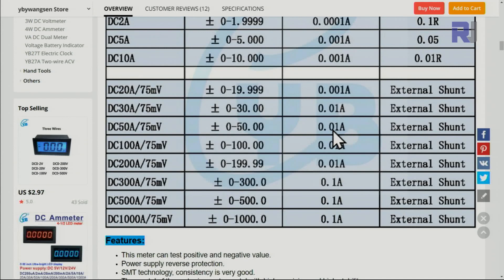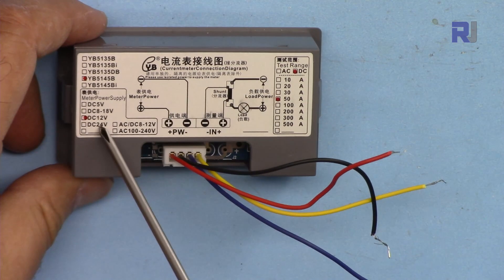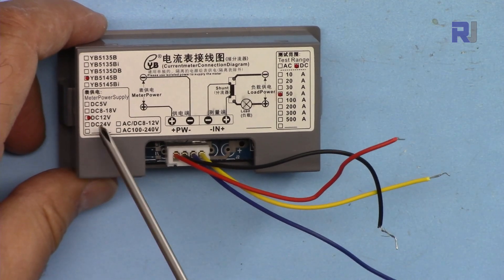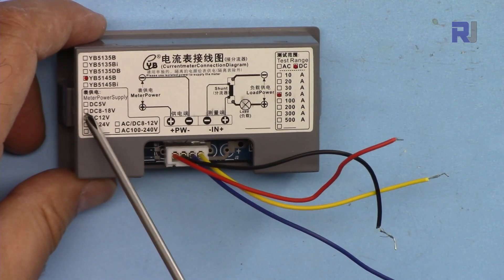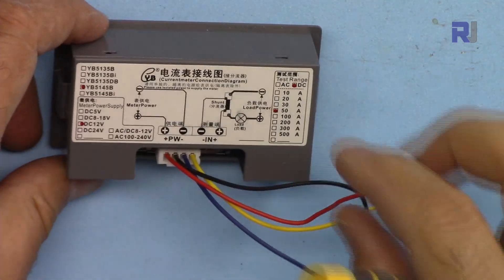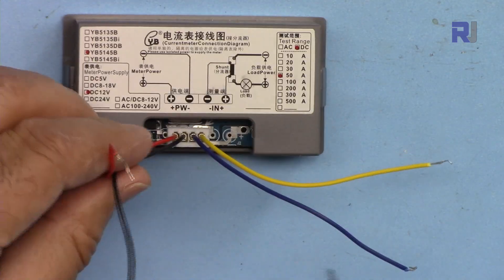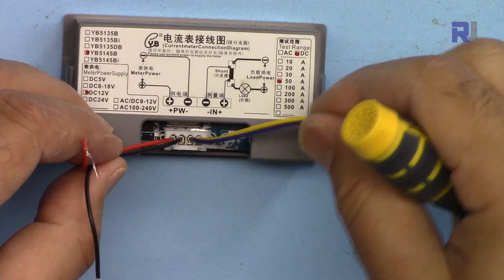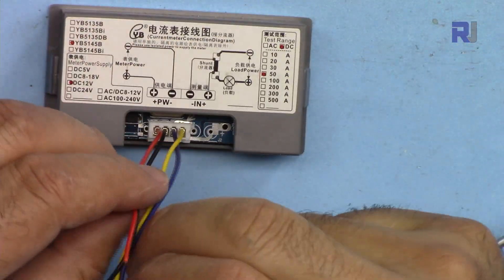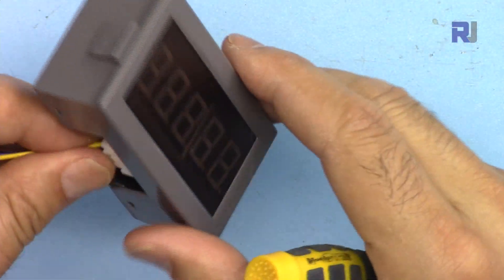50 ampere 75 millivolts plus minus. It can go plus minus 50 which means you can reverse the polarity and it shows minus 50. The resolution is 0.01 ampere or 10 milliampere. The sensor is external shunt module as labeled here for 12 volts. The same module can be modified for different versions. The wiring is clearly explained. We have two wires that will be connected to power supply, these two wires will go to the 75 millivolts shunt, and there is no other setting.